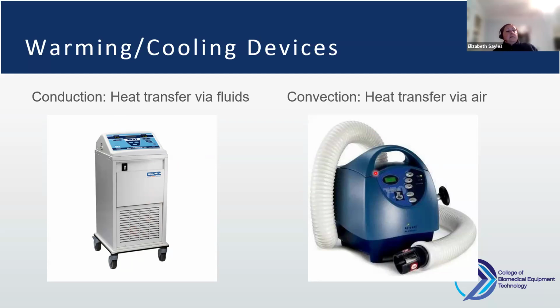On the other hand, the convection type devices - this is called a Bair Hugger, spelled B-A-I-R rather than B-E-A-R, no idea why it's spelled that way - these devices don't really have a lot of maintenance to them. You may end up replacing some filters. Sometimes these keypads, because they get pressed so often, you end up having to replace those frequently.